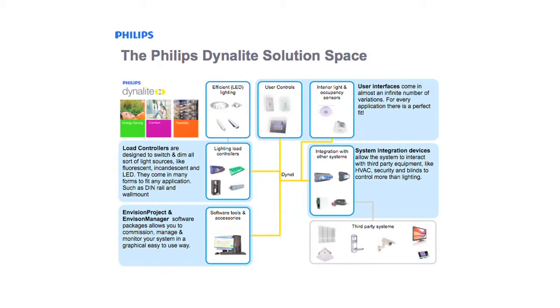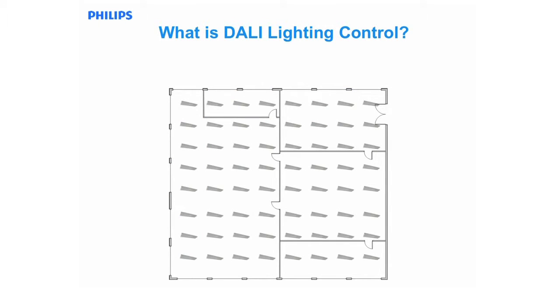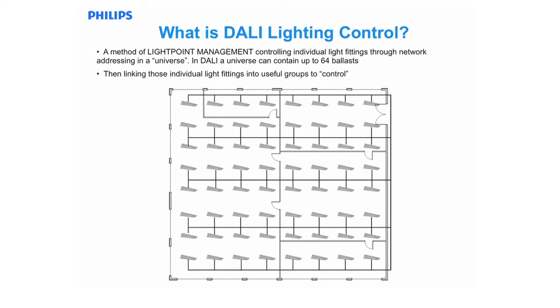DALI defines a network of lamps and controllers as a universe. In a DALI universe, all light fittings within a project are connected together on the same network. The DALI system assigns each light fitting a unique network address, which allows a lighting control system a method of sending instructions to individual light fittings, adjusting them to different levels if required.